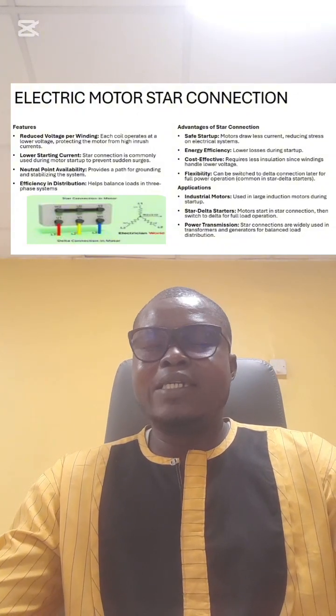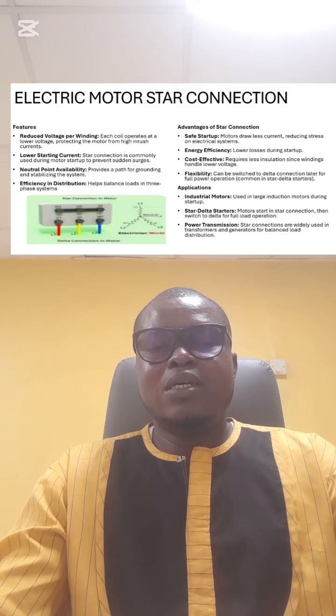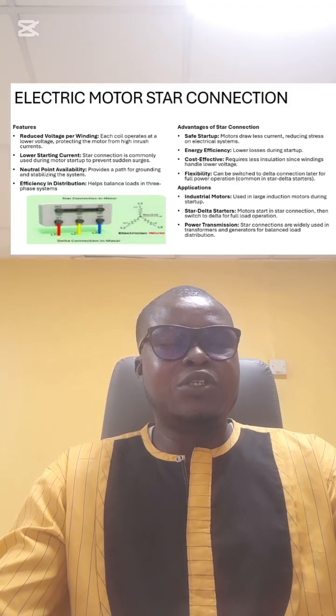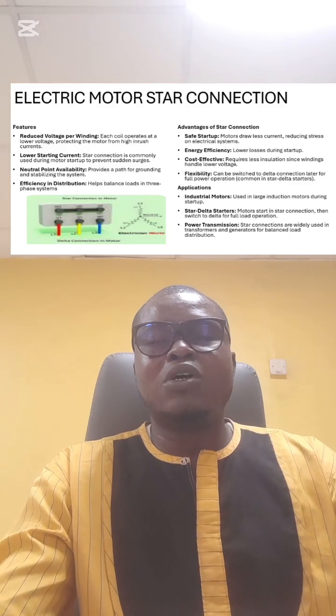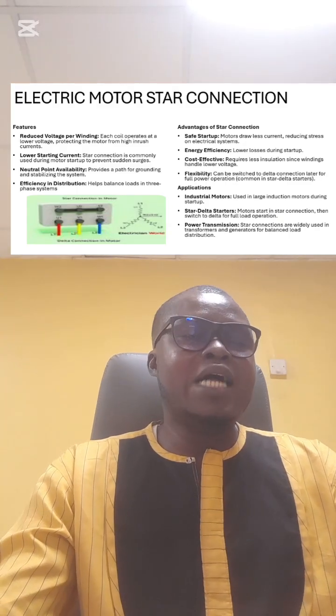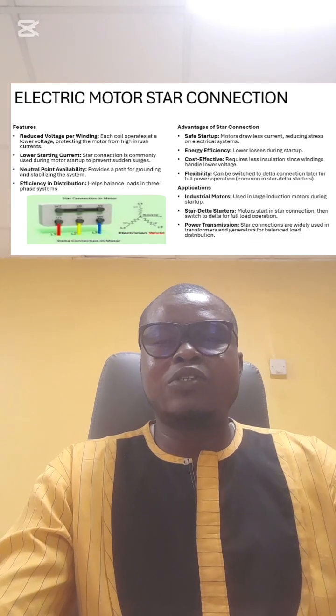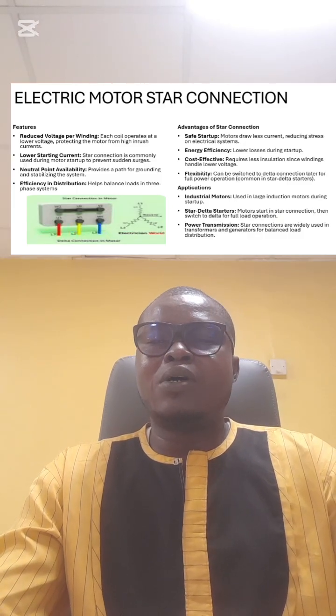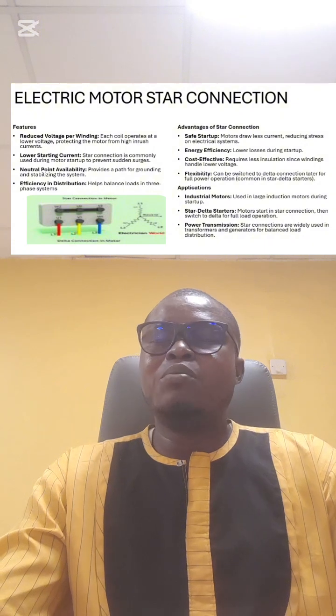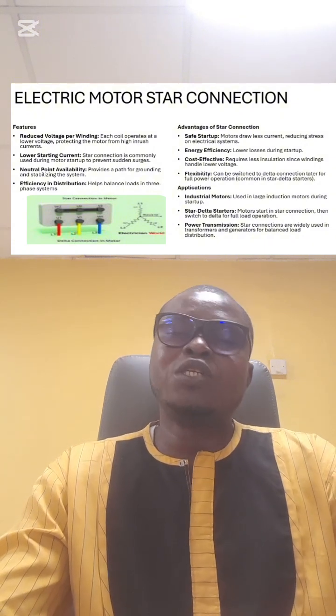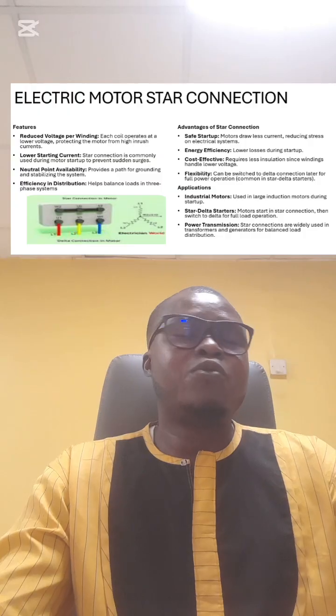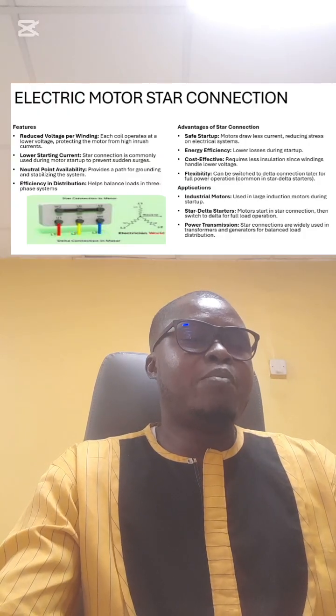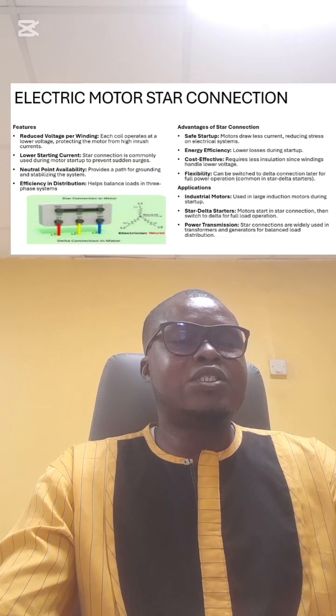I want us to understand that there are applications of this star connection. One of the applications is industrial motors, used for large induction motors during startup. Another application is the star delta starter. The motor starts in a star connection, then switches to a delta for full load operation. Power transmission is also an application. The star connection is widely used in transformers and generators for balanced load distribution.